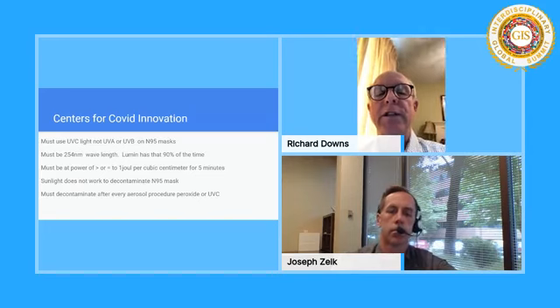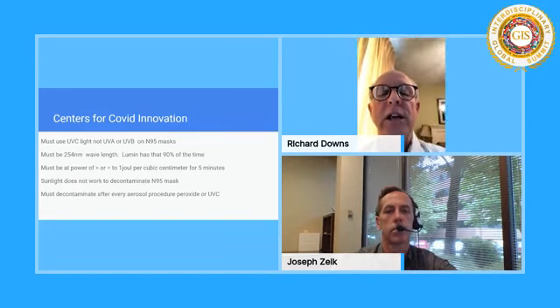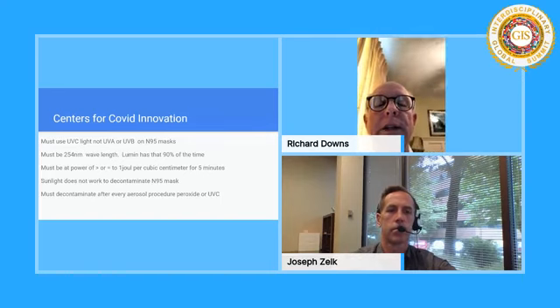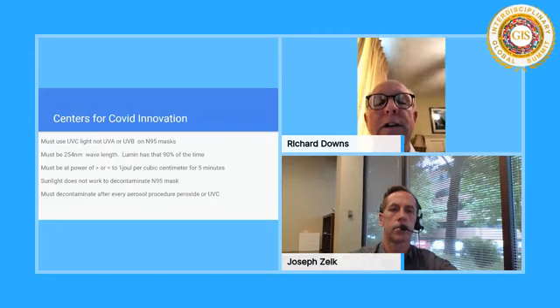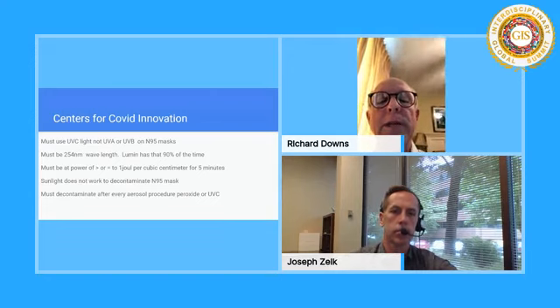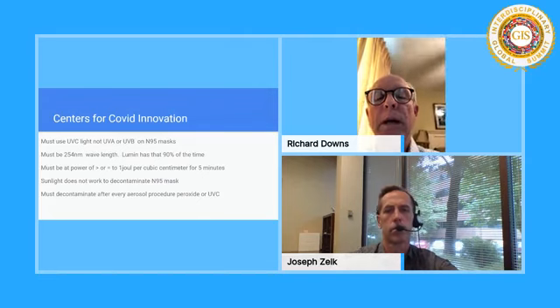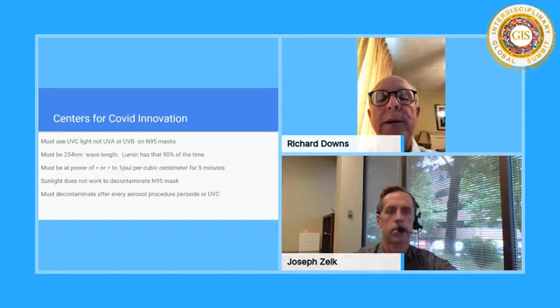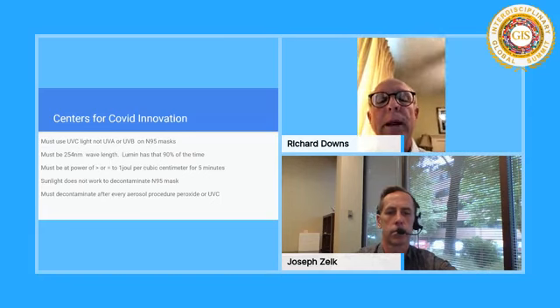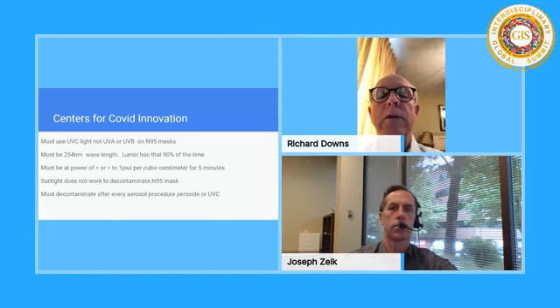Okay, this information comes from the Centers for COVID Innovation. And you can see that UVC light is recommended, not UVA or UVB, for any N95 mask. So it must be a 254 nanometer wavelength, and Lumen has that. At 90% of the time that it's on, it will do that at 254 nanometers. It must be at a power of greater than or equal to 1 joule per square centimeter for 5 minutes. Sunlight does not work for decontamination of N95 masks. You must decontaminate after every aerosol procedure with peroxide or UVC. This is what the Centers for COVID Innovation has written, and I agree with it completely. Next.